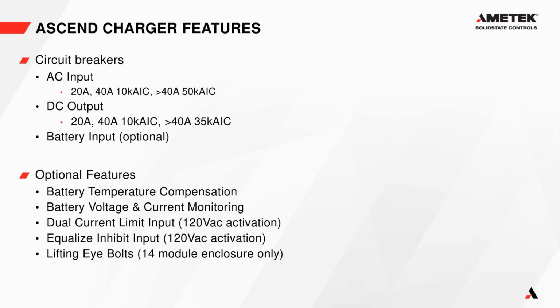The same goes for our equalize inhibit dry contact. It will prevent an equalize if, like I said, you have a fan failure or some other situation where you'd want to prevent equalize operation. And then we also offer lifting eye bolts on the 14 module enclosure.